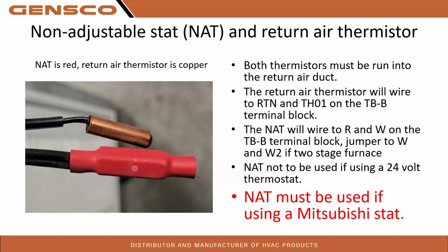This is only used if you're using a Mitsubishi controller. The reason we have that is because the Mitsubishi thermostats, your MHK2s, your Kumo Cloud, MA controllers, are all still powered by your heat pump and in communication. So if you drop communication or you lose power to your heat pump or anything like that, your thermostat is going to go down with it. This non-adjustable stat set for 65 degrees will give them temporary heat in that house. It'll maintain 65 degrees using the gas furnace. That's why, if we have a two-stage, you want to make sure to put a jumper between W1 and W2. That way we can bring that second stage heat on.